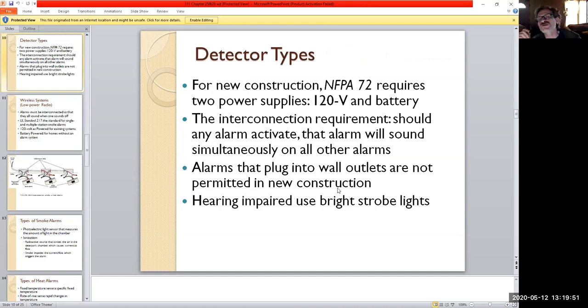For any new construction, NFPA 72 requires two power supplies: a 120 volt line going to it and a battery backup. This is pretty standard. They do allow grandfathered units, built before this requirement, to just have battery backup alone. Those are still allowed to exist. But if you upgrade, you're now required to install a 120 volt line into those.